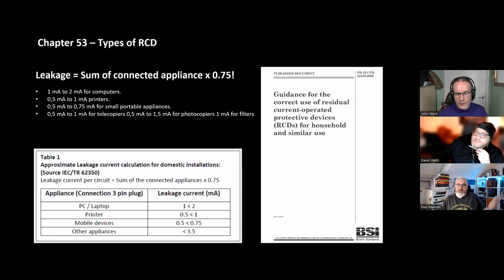I said this to the lads in Discord one night about doing EICRs retrospectively and stuff. I said, fundamentally, we're going to look at the installation today and look at how it's going to be used, the utilization of the system as in its condition now moving forward. And if you have a number of items that are going to potentially blind that RCD, then you cannot have confidence that additional protection is achieved anymore. And in those circumstances, you may as well assess that there's just no RCD there for the purpose of additional protection.